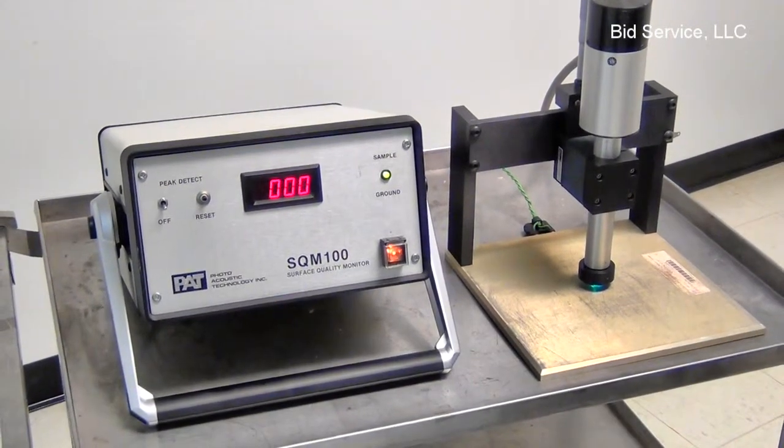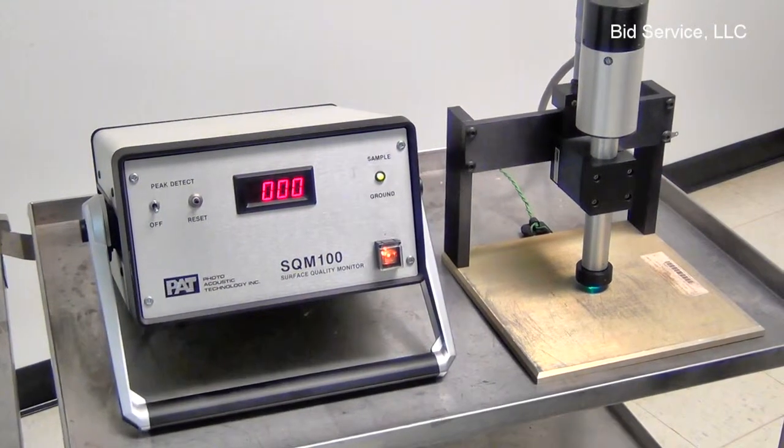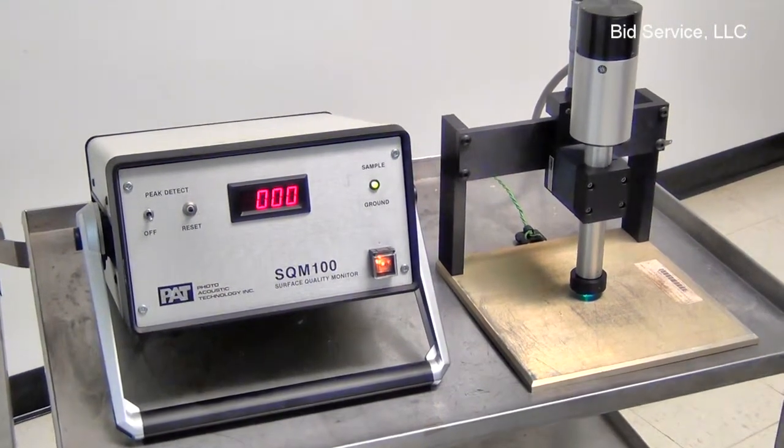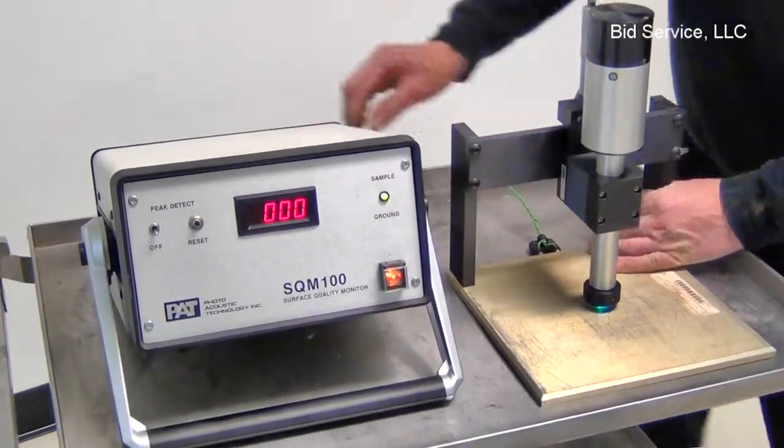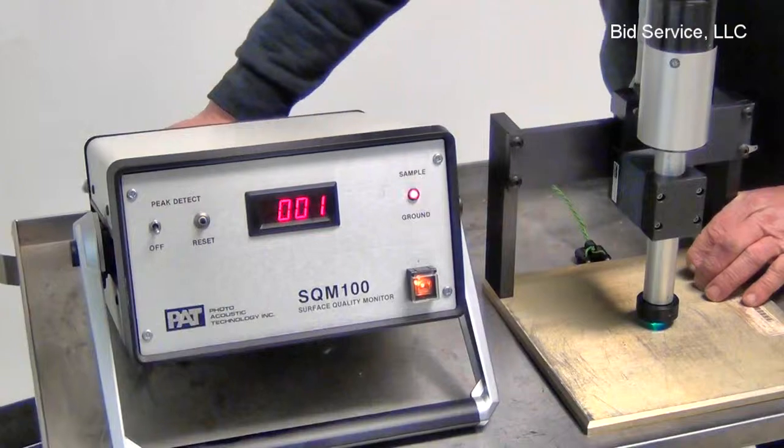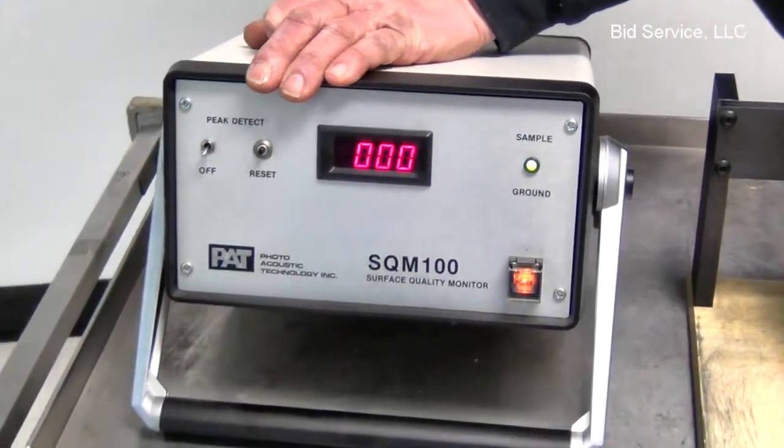It is also essential that the test surface to be monitored is well grounded to the console. If it fails to be grounded, a light will flash and you will not be able to achieve an accurate measurement.